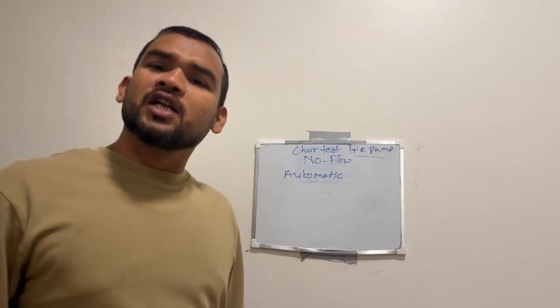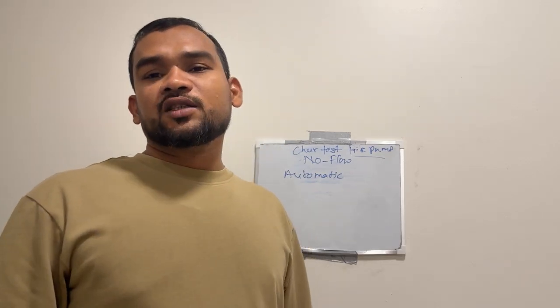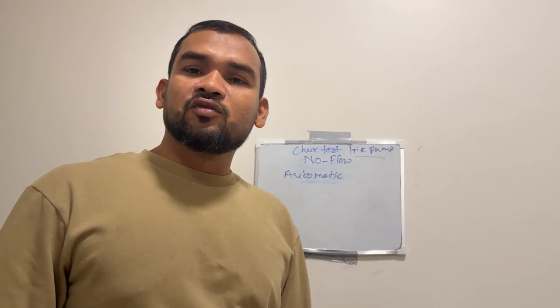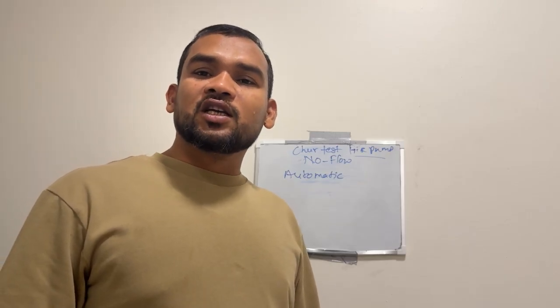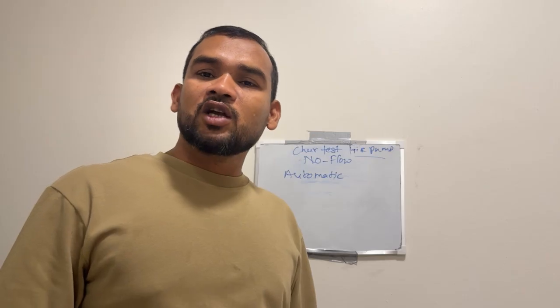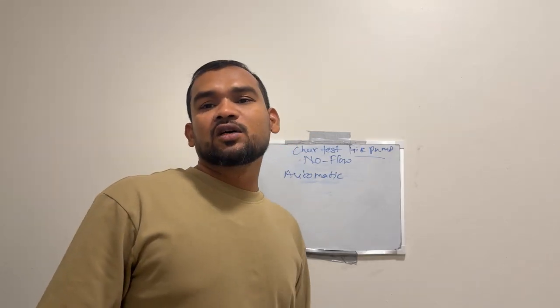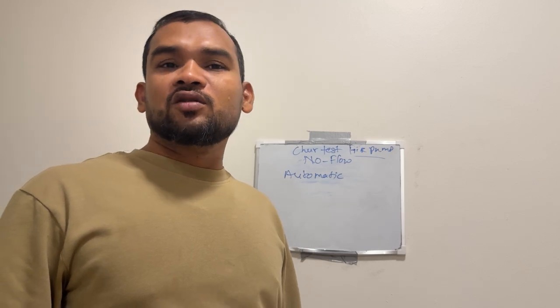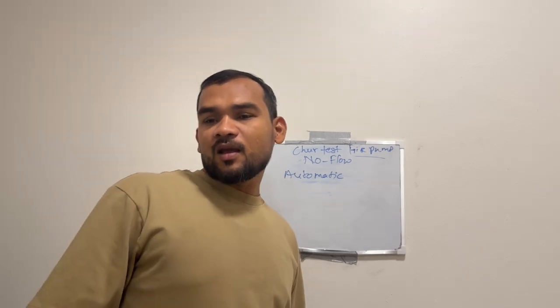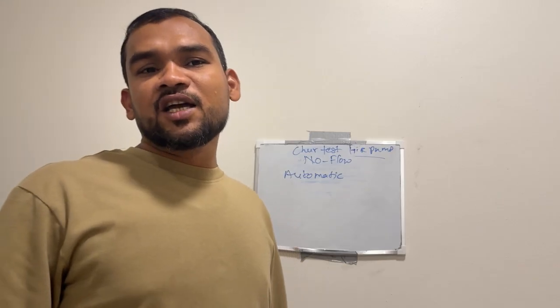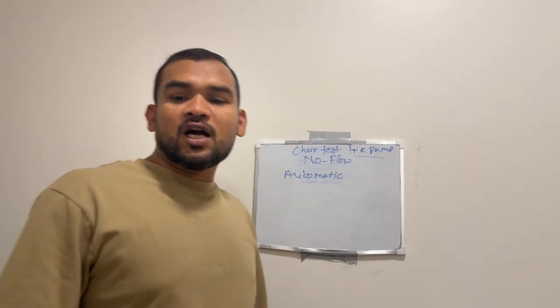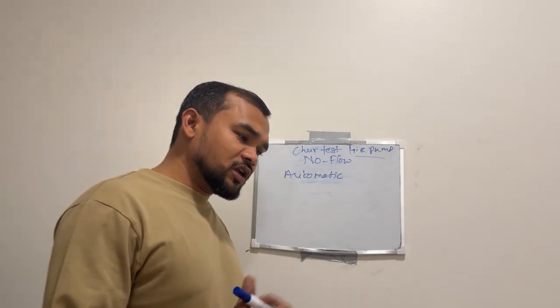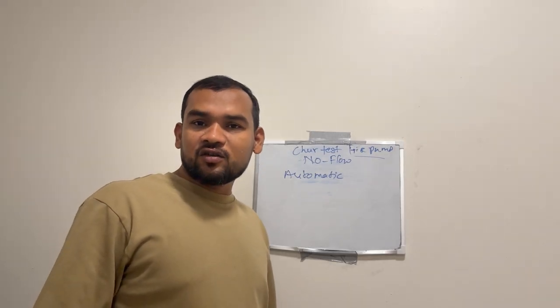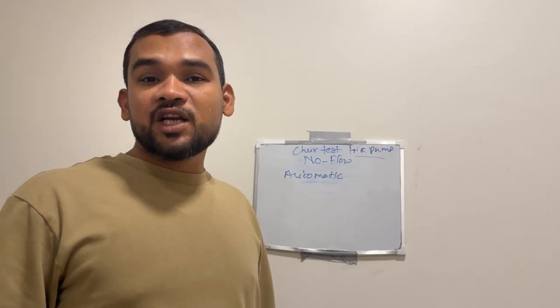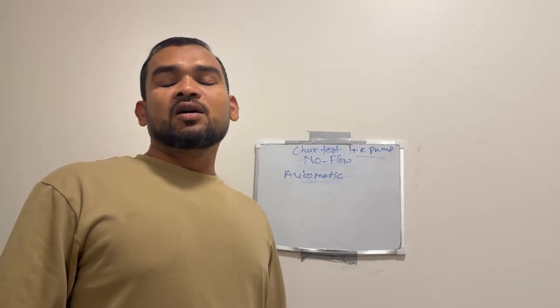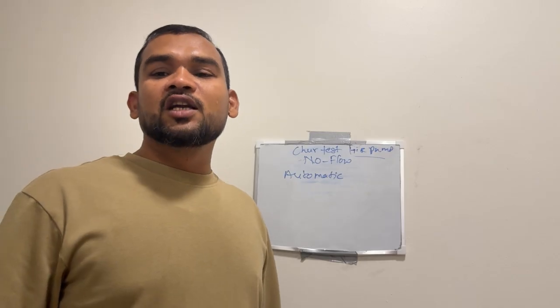We have to start automatically or manually. Generally we do the automatic test. Manually, we have to check one by one from the controller that the electrical, jockey, and diesel engine pumps start manually or not. Then we put the selector switch in automatic position, and we will start the test. We will drop the pressure from the test drain line, so the pump will start automatically. The jockey pump will run first to maintain the pressure, but if there is more pressure drop, then the electrical pump will discharge.